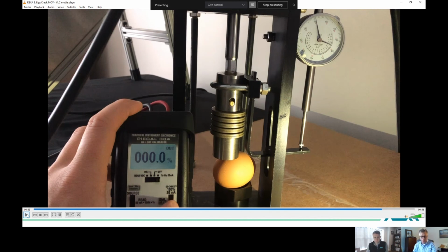How about speed? How quick can this actuator react? Yeah, so there's movement speed and reaction time. The speed that the actuator moves is something we determine in the sizing process, where we're understanding our customer's required torque or thrust, the stroke length, and how fast they need it to move, and we can specify different motor configurations for faster operation. The dead time, or how fast it's responding, the time before it moves, is in the milliseconds. So we're responding right away to the control signal change, initiating movement and going to position very quickly.